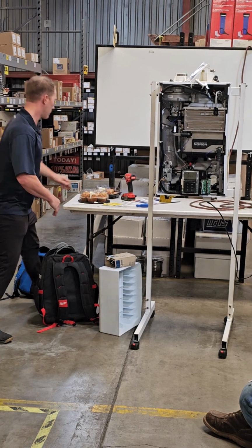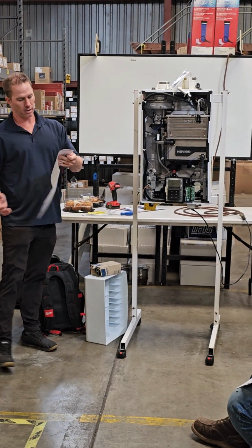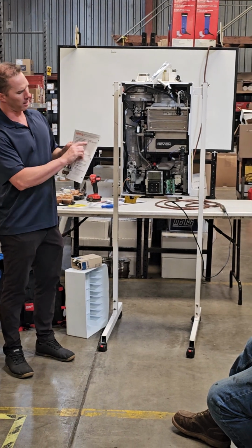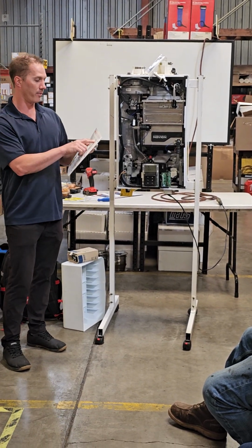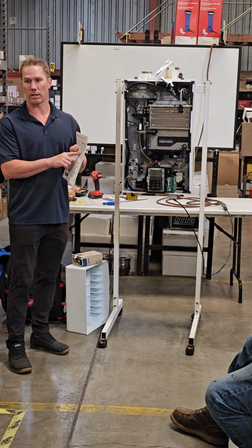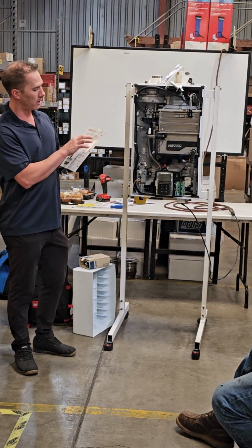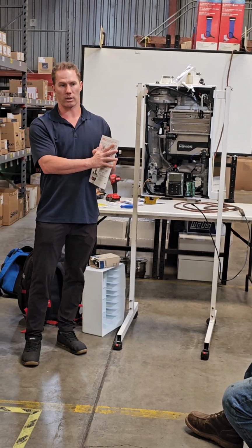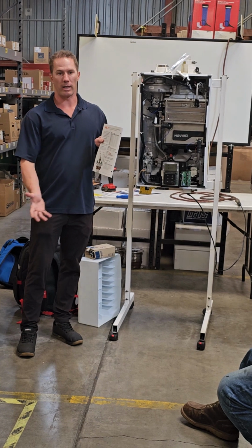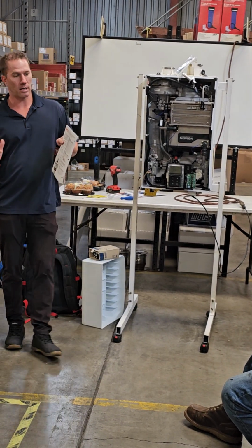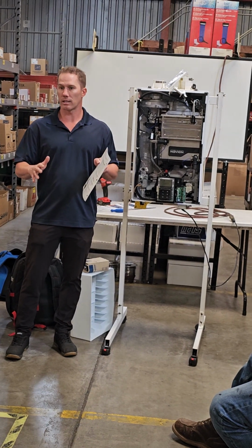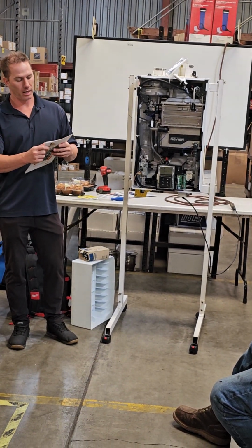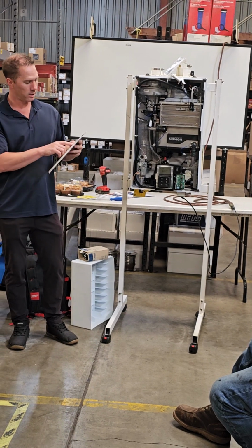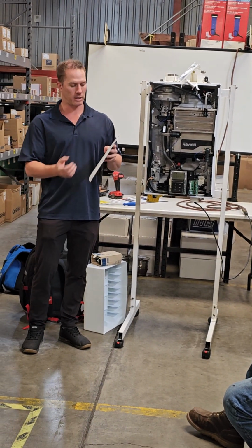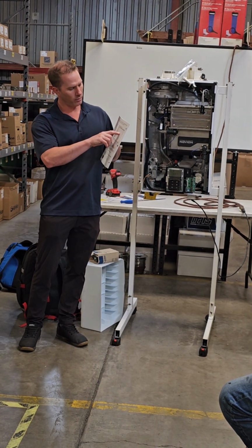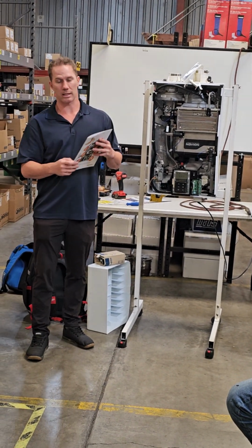And if you guys look at the front page of this guy right here, it's going to be the NPE-2 temperature rise chart. So this is going to tell you exactly how many GPMs you're going to get out of each of our units. Basically, the way tankless water heaters work is they take the ground temperature water and they raise it up to the set temperature. So around here, the temperature is about 60 degrees, plus or minus, winter, summer, hotter, colder. And then we always want it set at 120, so from 60 degrees up to 120, that's a 60 degree temperature rise. If you look over, our biggest unit, you're going to get 6.5 GPMs.